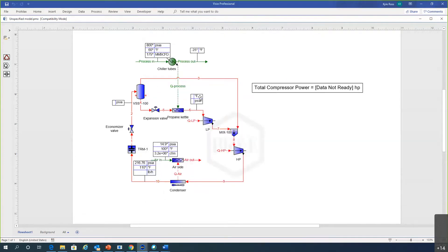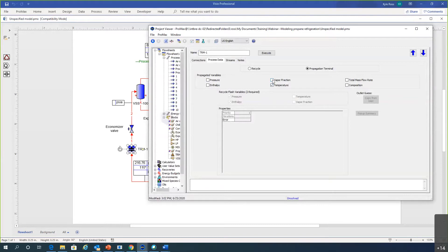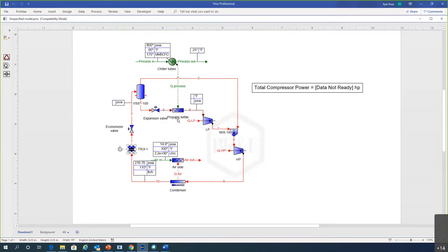ProMax knows the composition is 100 percent propane so it propagated that around the loop. In the propagation terminal, the two variables we know coming out of the condenser are the temperature — 110°F — and that it is a saturated liquid. So in the propagation terminal we specify temperature and vapor fraction to be propagated across. We also know the outlet of the low-pressure compressor must match the pressure of the vapor coming off the economizer for blending, so we use a specifier to set stream seven's pressure equal to stream three's pressure.